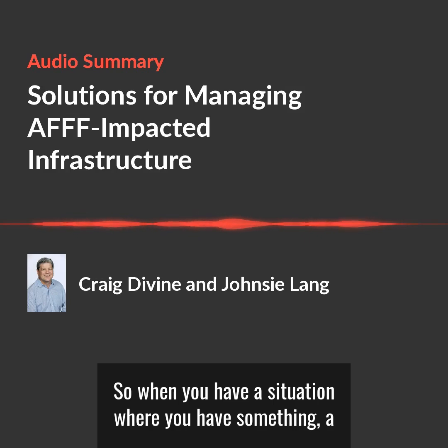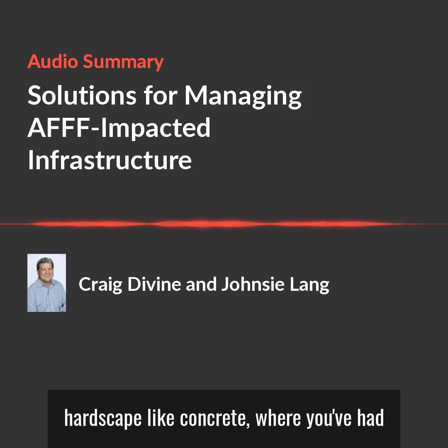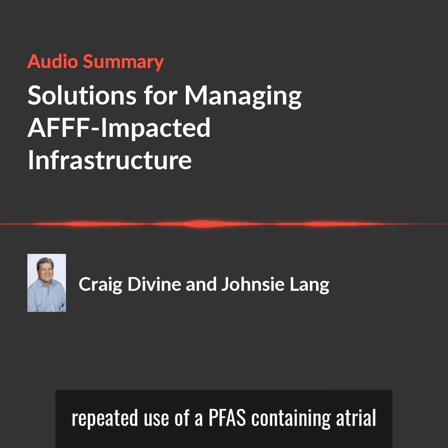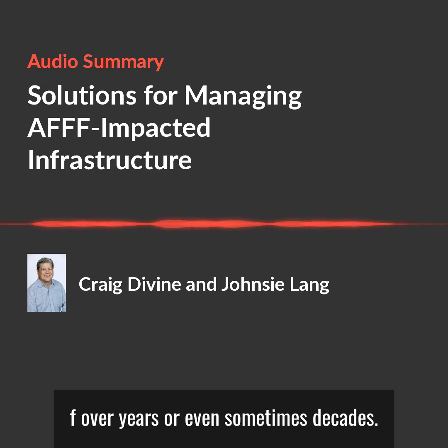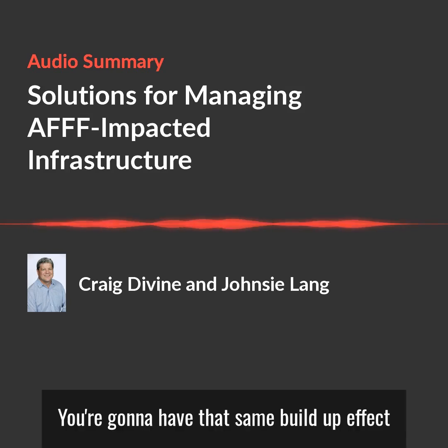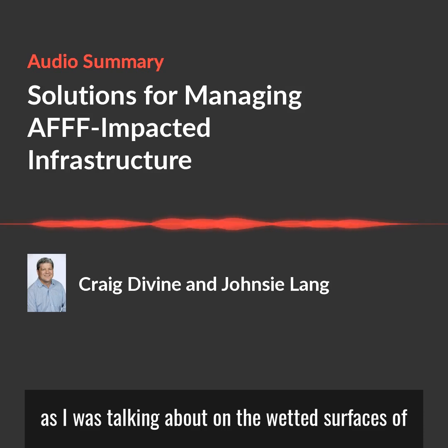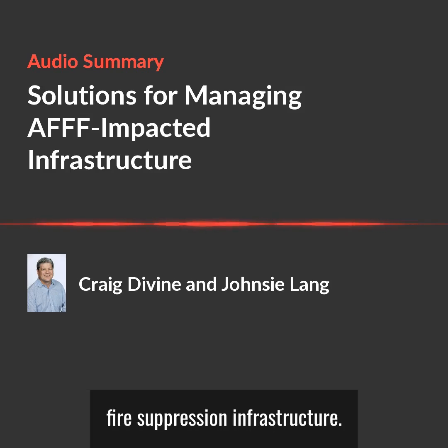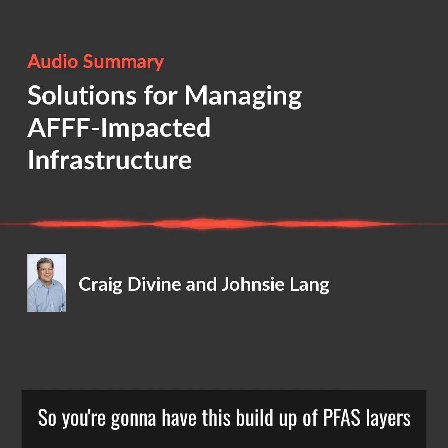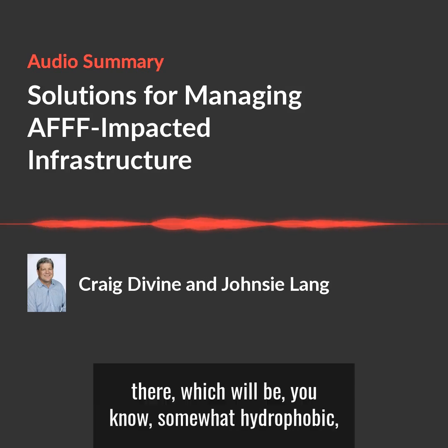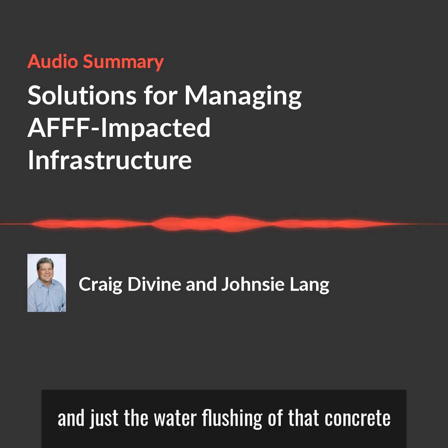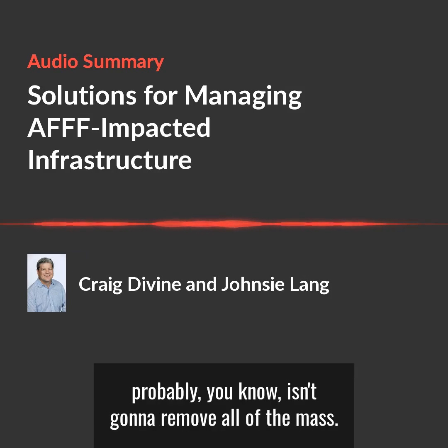So when you have a situation where you have a hardscape like concrete, where you've had repeated use of a PFAS containing AFFF over years or even sometimes decades, you're going to have that same buildup effect as I was talking about on the wetted surfaces of fire suppression infrastructure. So you're going to have this buildup of PFAS layers there, which will be somewhat hydrophobic. And just a water flushing of that concrete probably isn't going to remove all of the mass.